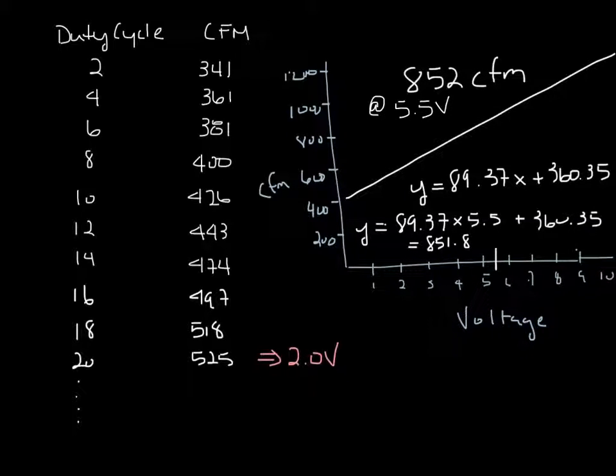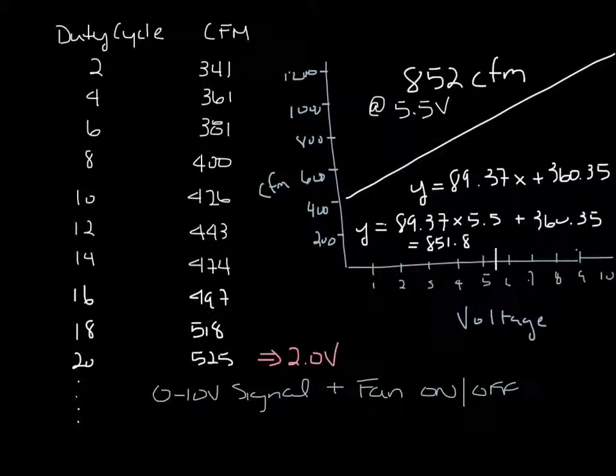So the two most common ways we see fan boxes controlled through the DDC controls depends on what outputs the control actually has. If a controller can use two outputs and send both a 0 to 10 volt signal and a fan on-off signal, then they would do that and get the full range of the 0 to 100% duty cycle. If the controls can't send the separate fan on-off signal, then they would send a 2 to 10 volt signal to control the fan speed, which gives you a duty cycle between 20 and 100%. Then any voltage under 2 volts would be off for the motor.